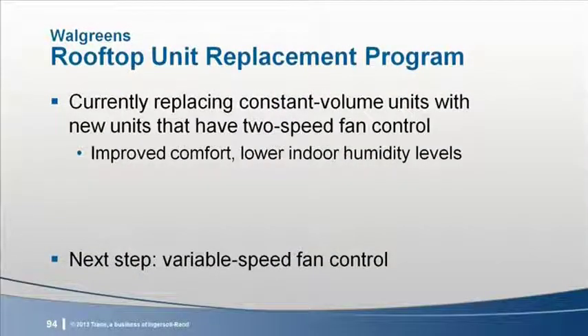So your considerations when you're making these decisions on whether to upgrade to high efficiency equipment, you talked about energy savings, which is probably one of the drivers, it sounds like. Other benefits that you were hoping to get from these 2-speed units? Yes, sir. To Akeem's point about the focus in Puerto Rico with the high utility rates, and Florida, areas like that, Walgreens has been seeing for years a lot of issues with humidity control. They have put in place hot gas reheat in the past. They looked and said it's probably better for us from a direct perspective to lower that airflow and take advantage of that dual stage motor and not have to necessarily utilize hot gas reheat. So Florida was the biggest area, I think, where we saw the greatest return with respect to direct humidity control.